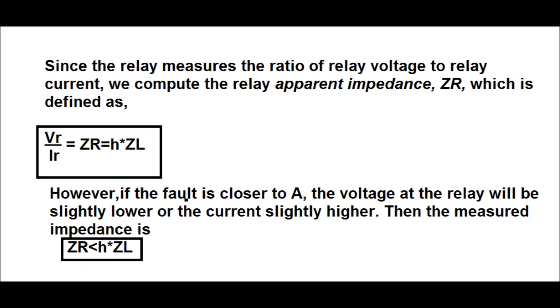Since the relay measures the ratio of relay voltage to relay current, we compute the relay apparent impedance ZR, which is defined as Vr / IR = ZR = H × ZL. However, if the fault is closer to point A, the voltage at the relay will be slightly lower or the current slightly higher. Then the measured impedance will be less than H × ZL and the relay will operate.